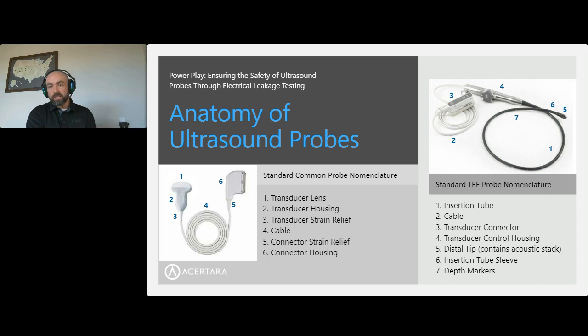No, if you wet the probe, it won't necessarily create damage. You have to soak it in water to be able to do your electric leakage testing. If you're cleaning the probe initially, these are generally pinprick holes or other small issues. The water getting in at that step, or the possibility of some of those disinfecting fluids getting in at that step, if you're using wipes or however you're doing it, is a minimal concern, only because we can't do anything else if the probe's not safe to handle, and safety for everybody else is really important. The damage actually occurs if you fail an electric leakage test, or the probe has one of those problems and gets fluid in, and then it gets plugged into a system and energized. When it's energized, that's when you blow up things. You turn all of your expensive electric components into smoke and light, and they don't like that.